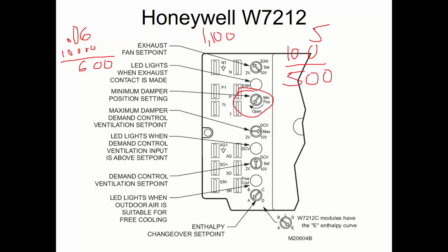On DCV, 600 goes in there. It becomes my new minimum. And 1,100 goes over here, my new maximum. And a DCV modulates me between these two things. My new minimum, which is the building part, and my regular minimum, which we call the DCV max to make you confused, is 1,100. And I modulate down from there when people don't show up for work at the building.